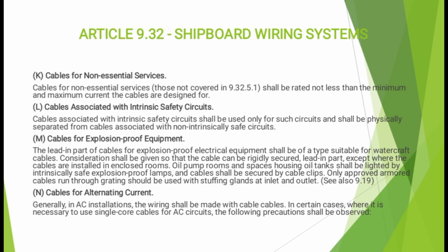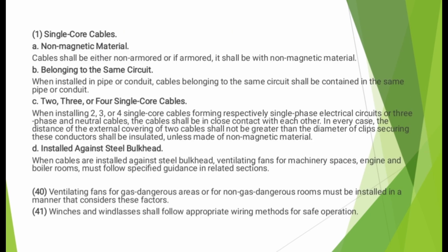Cables for alternating current. Generally, in ship installations, the wiring shall be made with cables. In certain cases where it is necessary to use single core cables for AC circuits, the following precautions shall be observed. Single core cables, non-magnetic materials. Cable should be either non-armored or, if armored, it shall be of non-magnetic material, belonging to the same circuit. When installed in pipes or conduit, cables belonging to the same circuit shall be contained in the same pipe or conduit. 2, 3, or 4 single core cables. When installing 2, 3, or 4 single core cables forming respectively single-phase circuits or 3-phase and neutral circuits, the cables should be in close contact with each other.